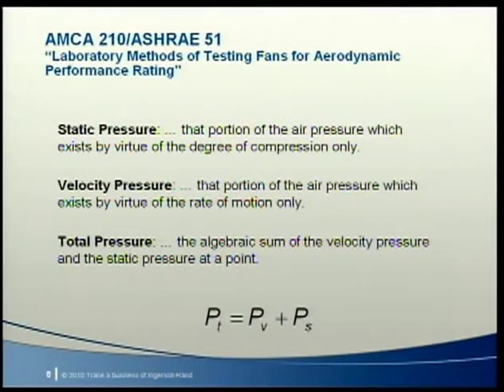Today we're going to talk about mechanical fans — the heart of every air distribution system. Fan fundamentals begin with air pressure. Air in motion has both potential and dynamic energy. Potential energy relates to static pressure, like air in a balloon. Dynamic energy relates to velocity pressure, like air pushing on a sail. The total pressure of air in motion is its static pressure plus its velocity pressure, and a fan increases the total pressure of air passing through it.